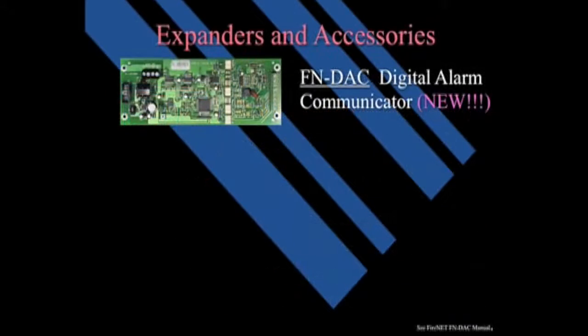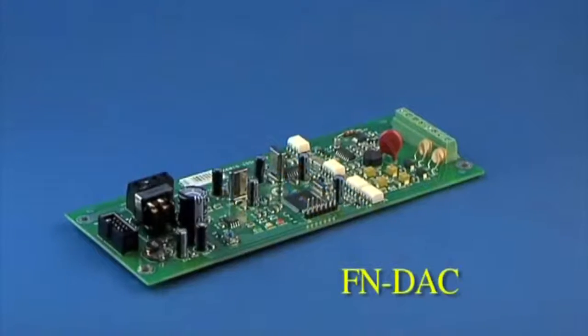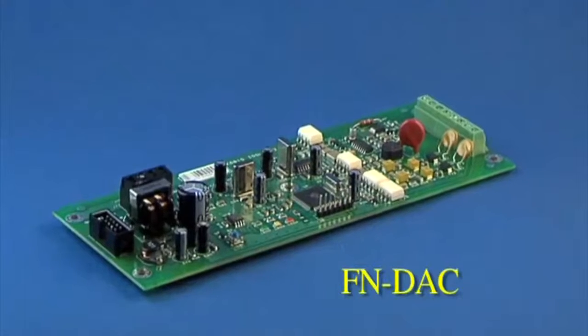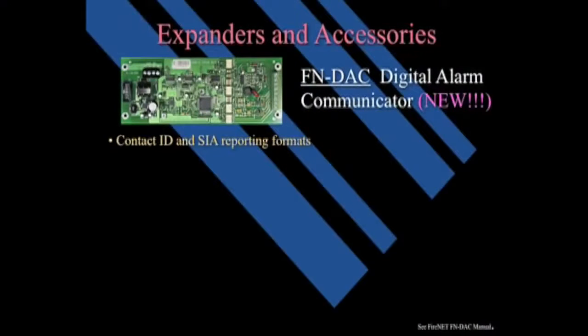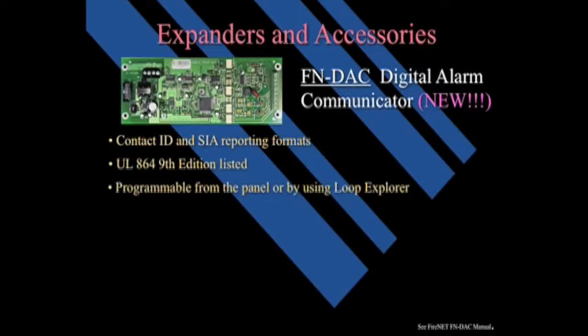The FN-DAC digital alarm communicator is also new for 9th edition. This dialer supports contact ID and SIA reporting formats. It's UL listed for 9th edition. It's programmable from the front panel or by using Loop Explorer. This dialer is able to report by zone or by address.